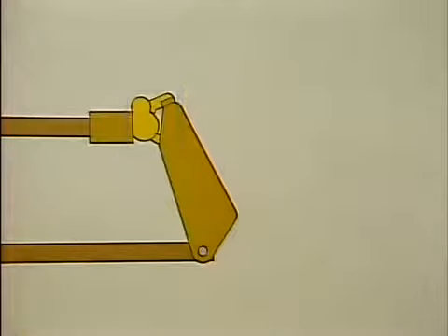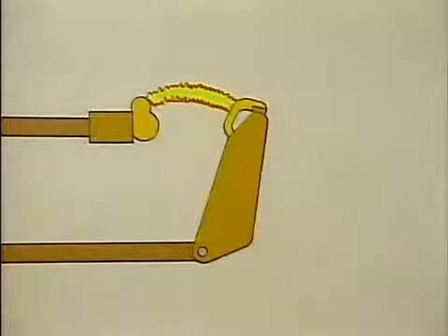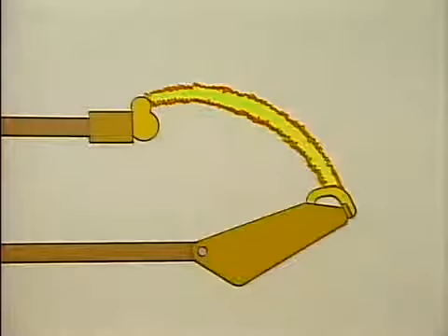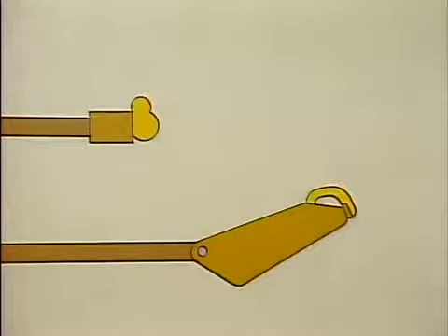To break the circuit, the speed at which the contacts separate is important, because the faster the contacts open, the less time there is for an arc to form and maintain itself. When the contacts separate rapidly, there is little time for the space between the contacts to heat up and become a conductor.